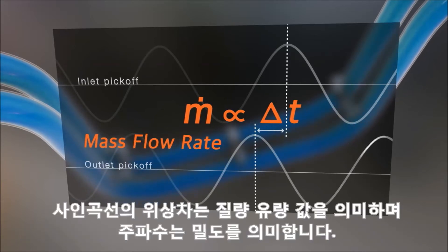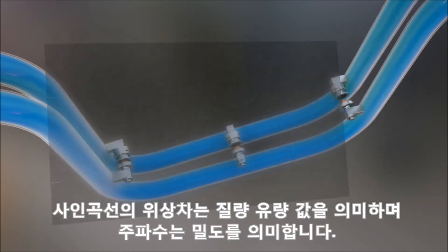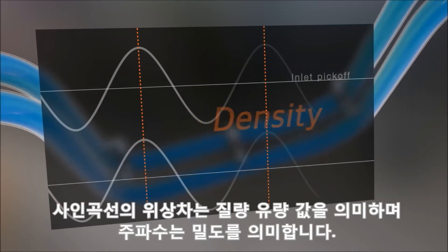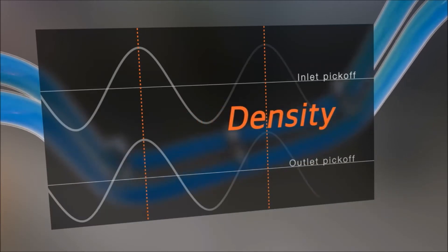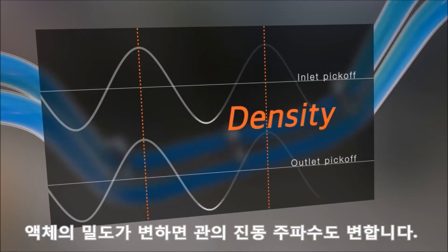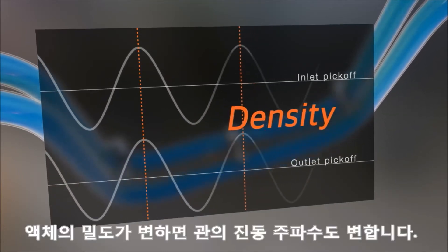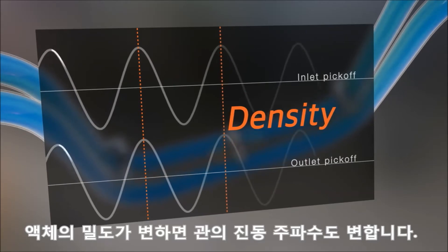While the sine wave phase shift indicates mass flow, the wave frequency indicates density. When the liquid density changes, the vibrating frequency of the tubes also changes.